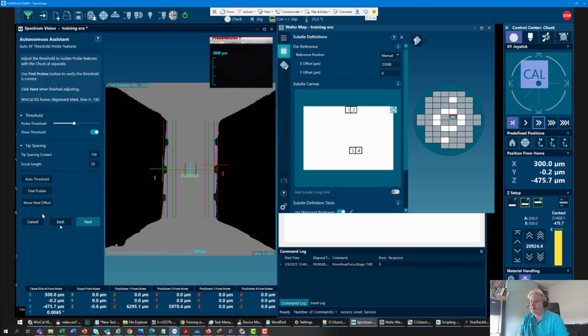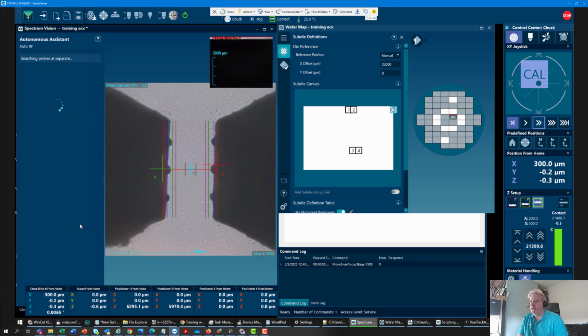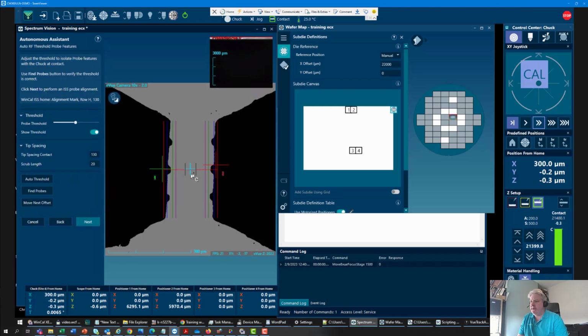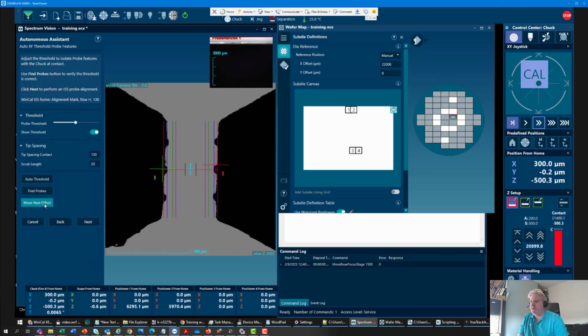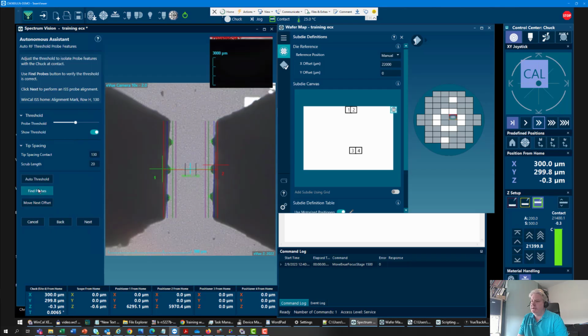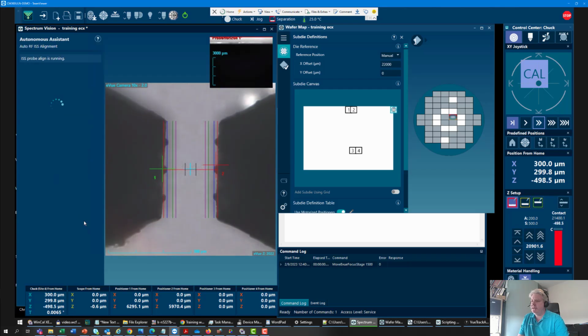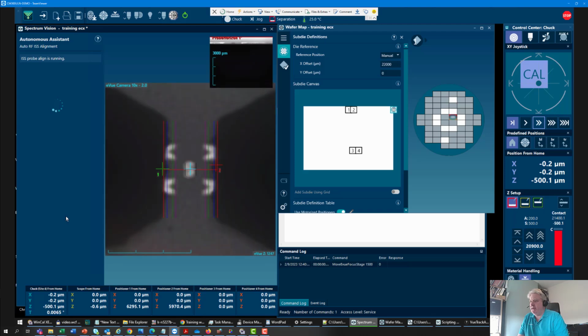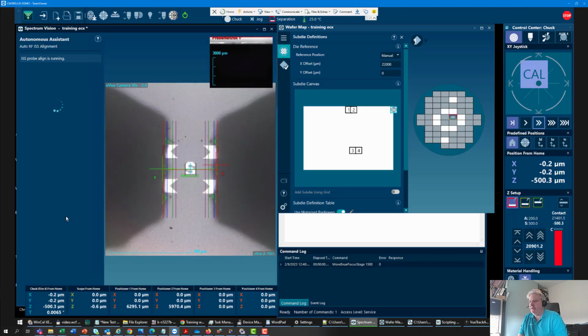So made contact. You can see a bit of contaminant there. Let's maybe move to another offset location, to another region of alumina where it's not so dirty. So that's good. So identify that. Yeah, that's fine. So now it's been trained, so it knows how to find the probes, make contact and separate. And basically, it's now going to iterate the probe spacing and overdrive using the motorized positioners in order to get all the contacts good.